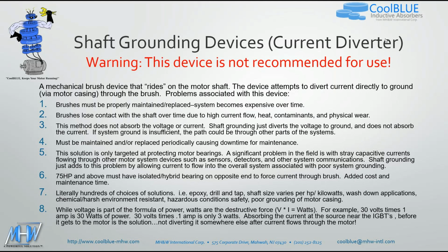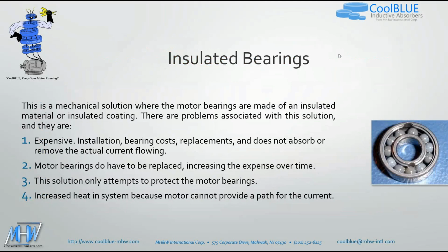So the next solution would be insulated bearings. Again, this is a mechanical solution where the motor bearings are made of an insulated material or insulated coating. There are definitely problems associated with this solution too. Number 1, they're expensive. The insulated bearing costs, replacements, they do not absorb or remove the actual current flowing. Number 2, motor bearings do have to be replaced, increasing the expense over time. Number 3, the solution only attempts to protect the motor bearings. And number 4, the increased heat in the system because the motor cannot provide a path for the current.